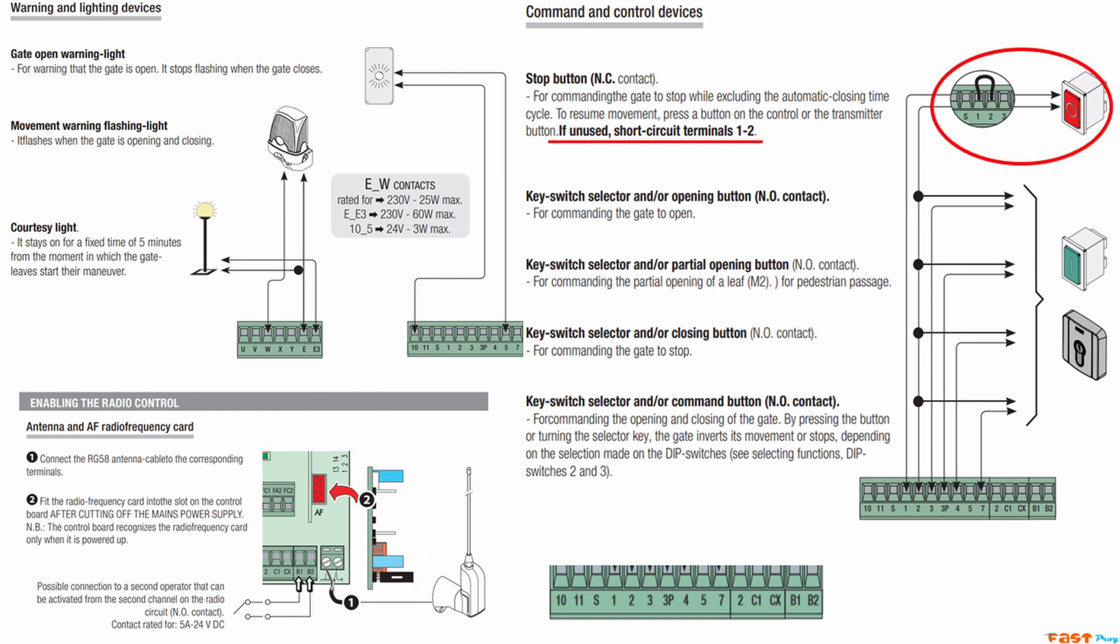If you don't have an emergency stop button connected between terminals 1 and 2 of the ZA3P, then make a jumper between these two terminals. Also, if you don't have photocells connected to terminal C1, make a jumper between terminals 2 and C1.